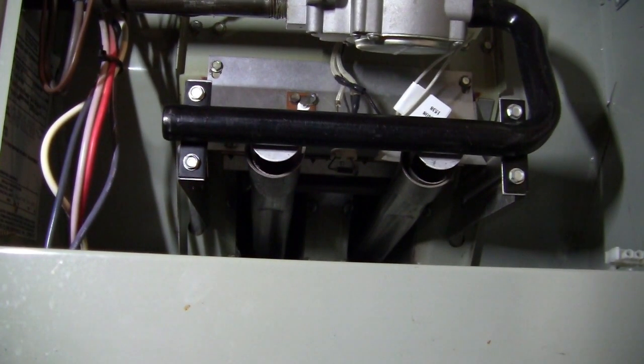This unit has a 45-second delay before it starts to send gas to the unit. So let's see. Now, the first thing is the controller turns on the fan. Once the fan turns on, the vacuum sensor will detect the vacuum. After the vacuum is detected, it sends a signal to the controller to turn on the igniter.